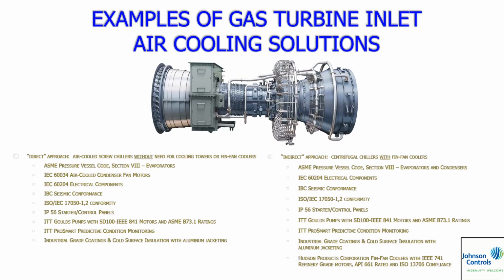Okay, the difference between a direct and an indirect is a direct is an air-cooled system where we have air-cooled heat exchangers for heat rejection, versus an indirect is typically centrifugal chillers with either cooling towers or fin fan coolers. Okay, normally fin fan coolers are used when you don't have water makeup. Usually you're close to the ocean, where a lot of these LNG sites are onshore. And so this analysis was centrifugal chillers with fin fan coolers, which is considered indirect. And the direct is we were using air-cooled screw chillers that did not need cooling towers or fin fan coolers. Okay, and then you had to meet all these different requirements. IEC, this is an international job, so I won't get into those gory details.